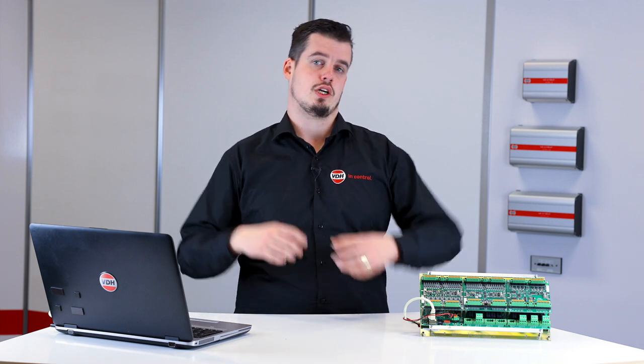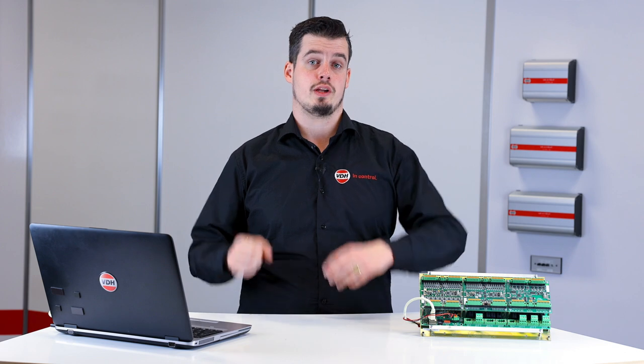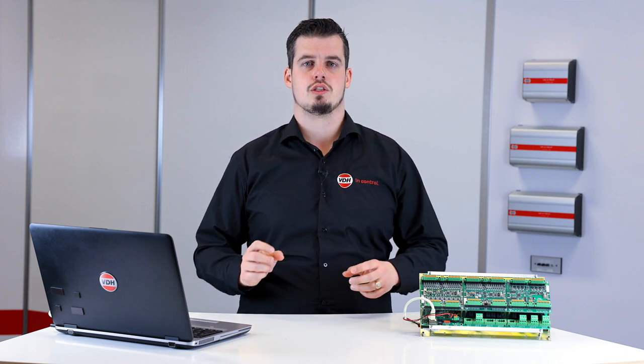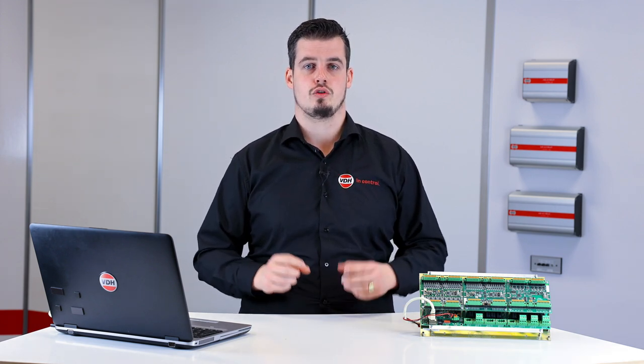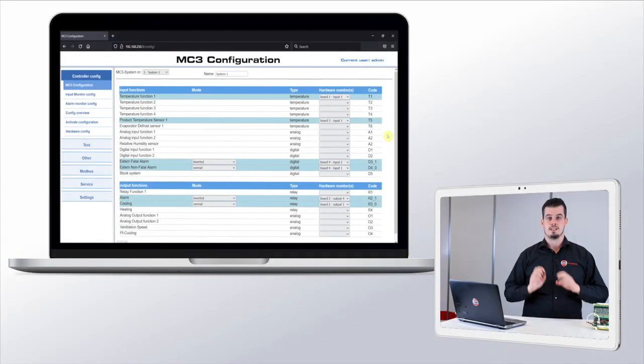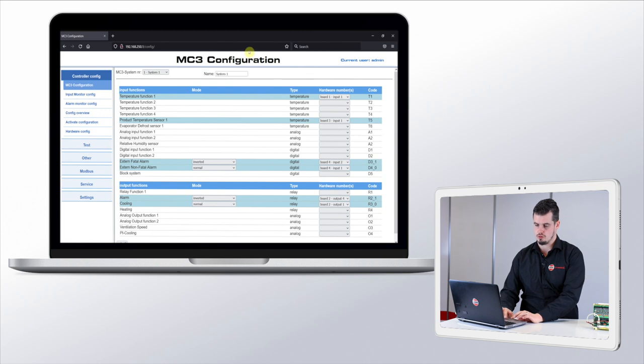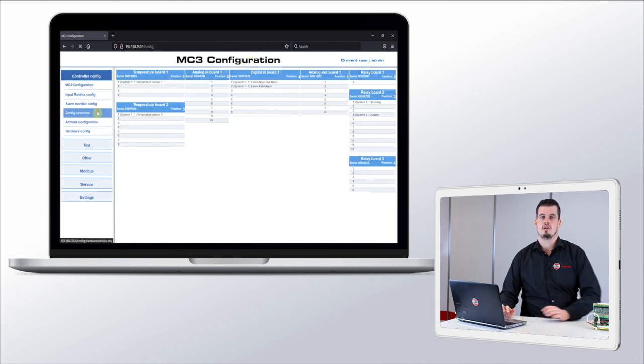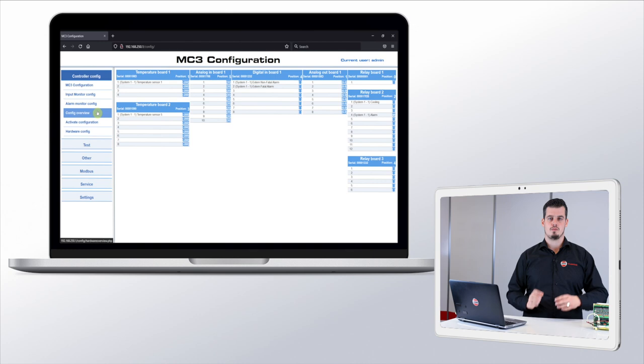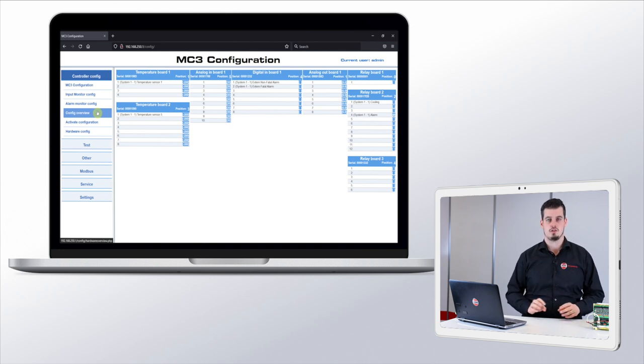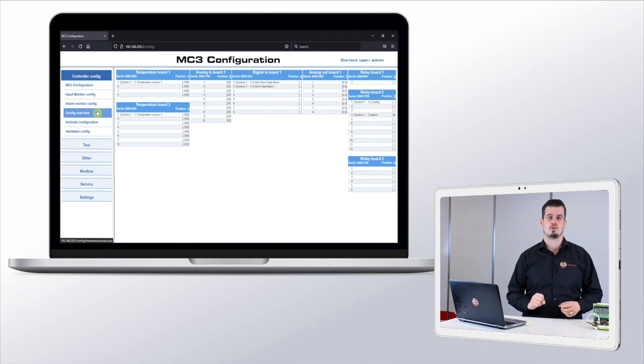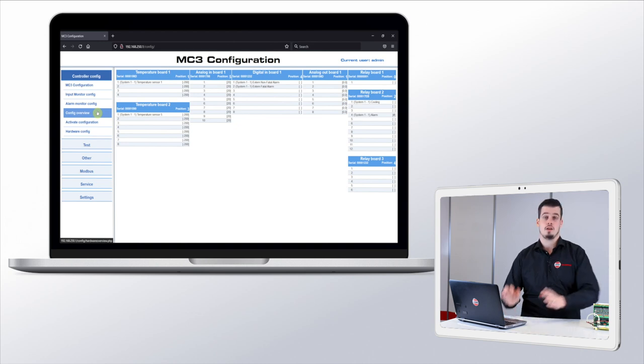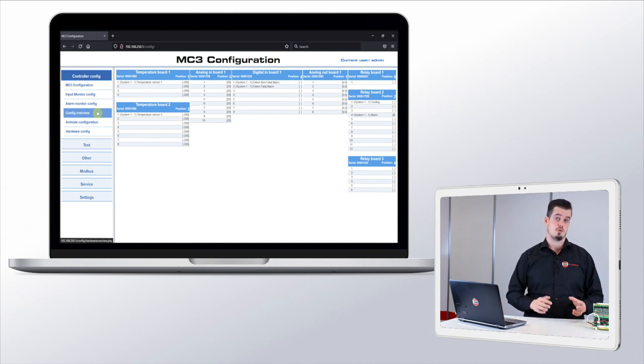After adding these inputs and outputs we want to check our work. Did we configure the functions to the correct input or output? We can do this by going by each of the functions one by one, but an easier option would be to use the config page of the controller. You can find this page here under controller config. In this page you can see the inputs and outputs present in your controller and the function you have configured to it. Next to this you can also see the current hardware state value of all of the inputs and outputs present within your MC3. We can check our work and we can see that we placed our functions on the correct inputs and outputs.